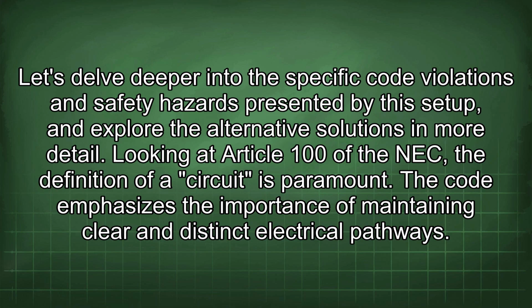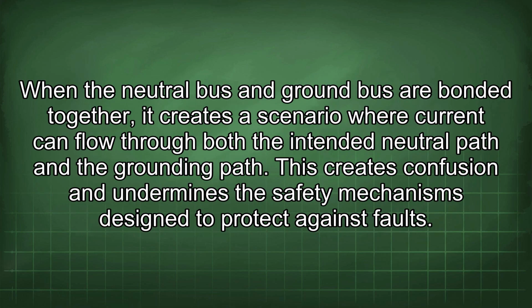in more detail. Looking at Article 100 of the NEC, the definition of a circuit is paramount. The code emphasizes the importance of maintaining clear and distinct electrical pathways. When the neutral bus and ground bus are bonded together, it creates a scenario where current can flow through both the intended neutral path and the grounding path. This creates confusion and undermines the safety mechanisms designed to protect against faults.